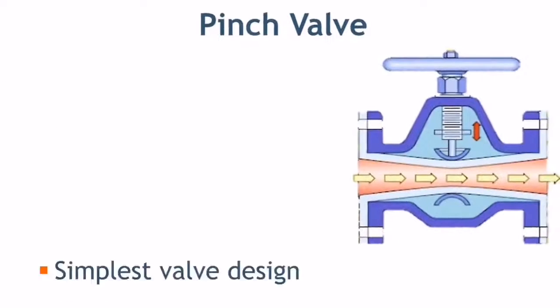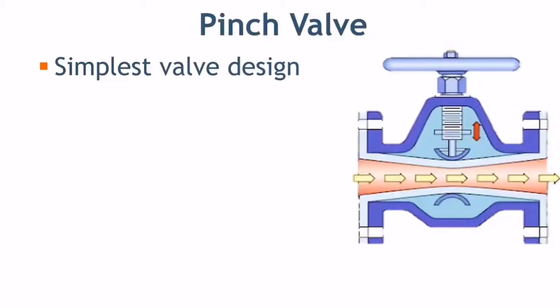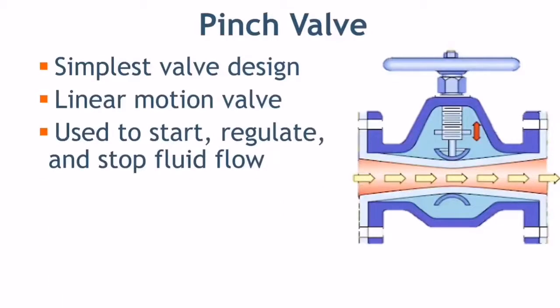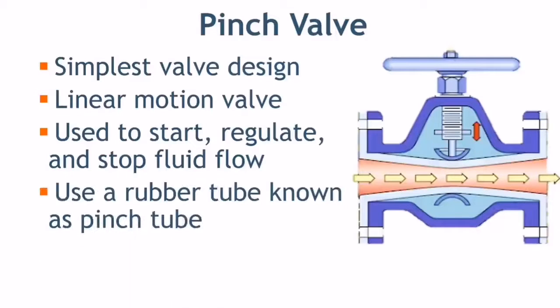The pinch valve, also known as a clamp valve, is a linear motion valve used to start, regulate, and stop fluid flow. It uses a rubber tube, also known as a pinch tube, and a pinch mechanism to control the fluid. Pinch valve is ideally suited for the handling of slurries, liquids with a large amount of suspended solids, and systems that convey solid material pneumatically.